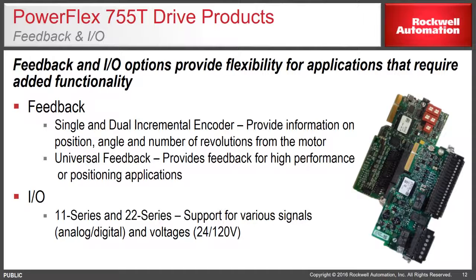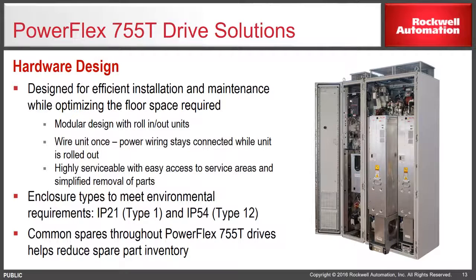Hardware. The 755T uses a modular design with roll-in units. You wire the unit once, the power wiring stays connected. Highly serviceable because with the rollout design, all parts are easily accessible. Enclosure styles include NEMA Type 1 and NEMA Type 12. There's common spares between all of the 755T drives. Helps minimize your spare parts inventory.